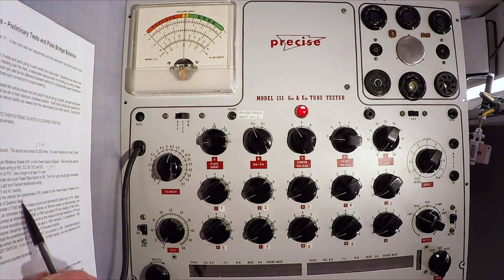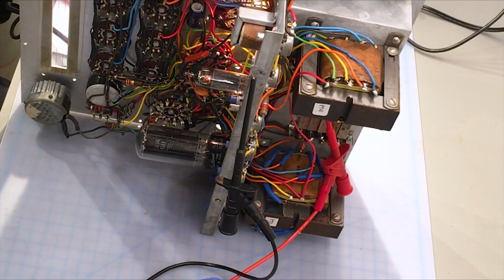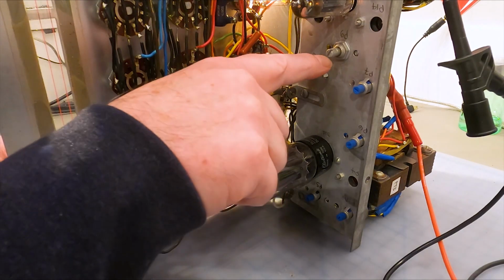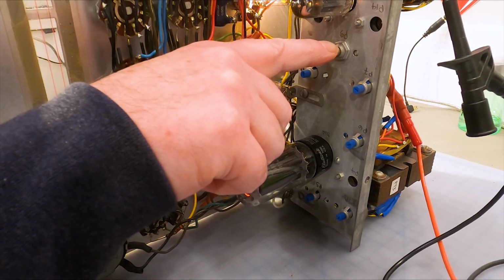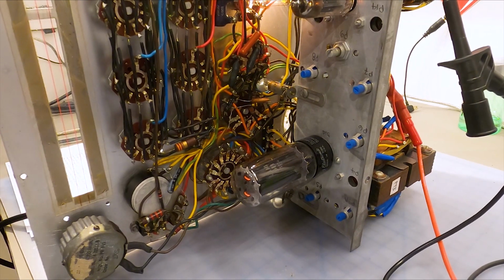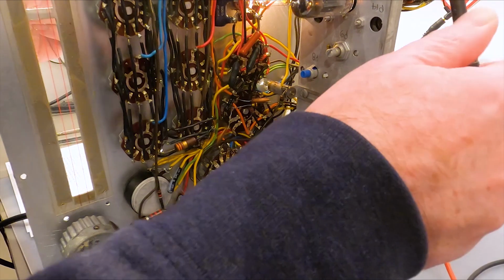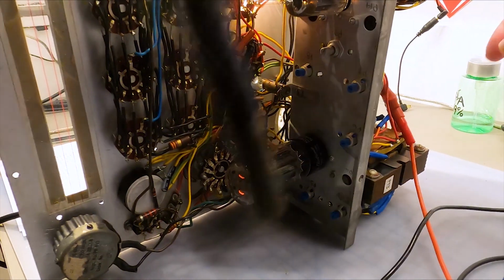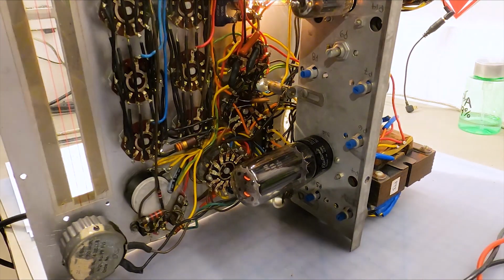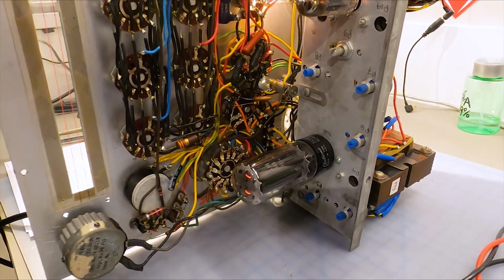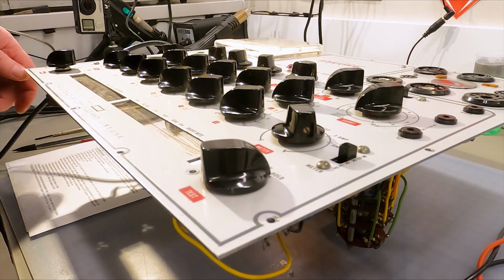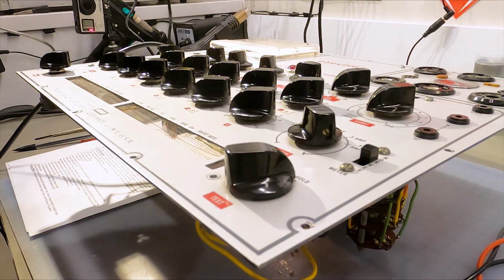5.03. So step 12 is, without changing any of the above settings, adjust the internal line potentiometer for a center scale reading on the tube tester meter. And I can do this, though there are a couple issues. So P9 is this potentiometer right here. However, one of the things we might want to be wary of is that we have the instrument tipped on its side. And so we'll disconnect from these voltage measurement points. And very carefully reposition the meter. We find that we're very close to that 0 point.